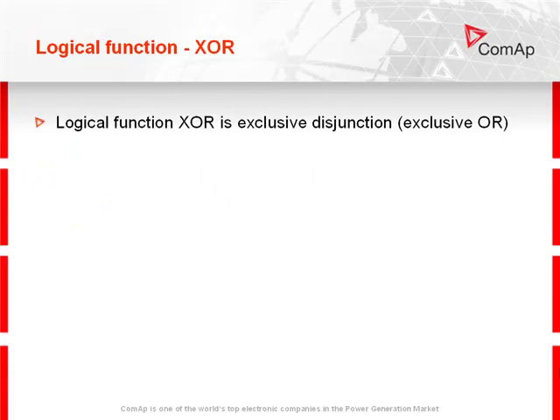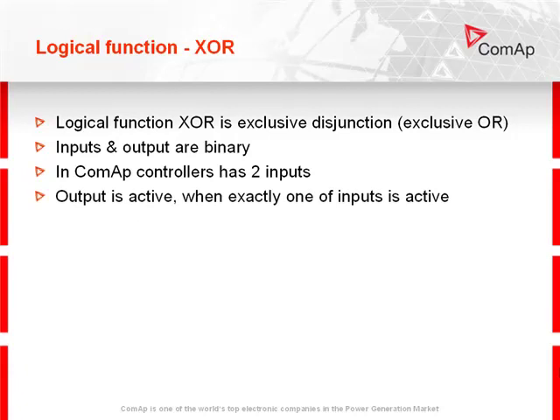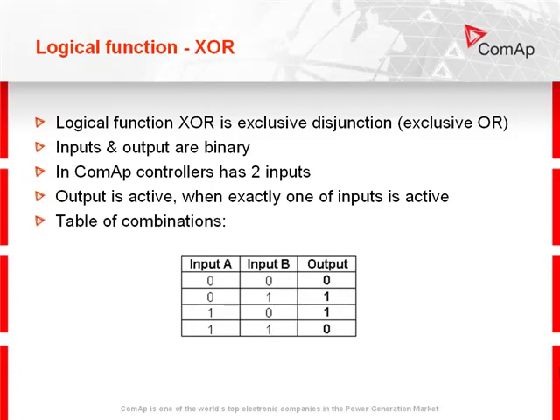Logical function XOR is exclusive disjunction, or exclusive OR. Inputs and outputs are binary. In ComAp controllers it has 2 inputs. Output is active when exactly one of the inputs is active. In the table of combinations you can see that exactly one active input causes an active output.